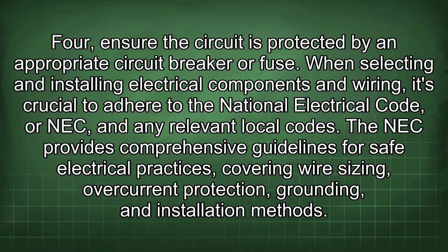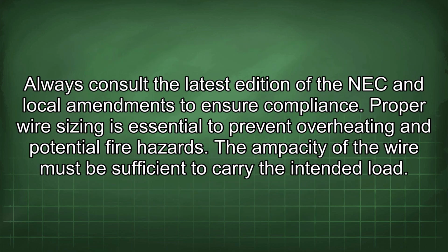When selecting and installing electrical components and wiring, it's crucial to adhere to the National Electrical Code, or NEC, and any relevant local codes. The NEC provides comprehensive guidelines for safe electrical practices covering wire sizing, overcurrent protection, grounding, and installation methods. Always consult the latest edition of the NEC and local amendments to ensure compliance. Proper wire sizing is essential to prevent overheating and potential fire hazards. The ampacity of the wire must be sufficient to carry the intended load.